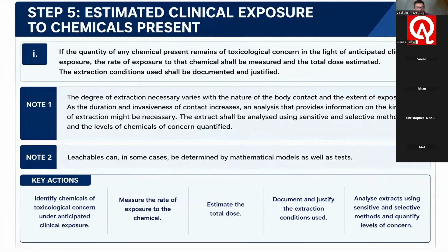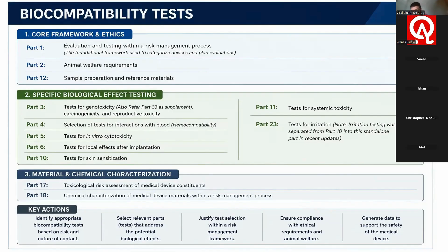So the overall biocompatibility tests, as we already discussed, are the general grouping and summary of the different series of the tests. Parts 1, 2, and 12 are the core framework of the overall series of biocompatibility tests. Parts 3, 4, 5, 6, and 10 relate to cytotoxicity, skin sensitization and irritation, hemocompatibility, and genotoxicity. These are the overall general tests recommended for biological effects in the standard, along with parts 11 and 23. For leachables and chemical characterization, we should follow parts 17 and 18. And depending on the different natures, you must consult the different parts.